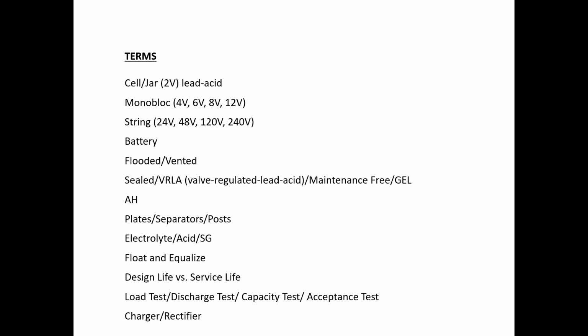Flooded and vented. We're going to talk about the two different technologies. From what I saw of your assets, primarily you are sealed valve regulated lead acid, and sealed is a misnomer. They are not sealed. They do have pressure release valves on them, but again, it was a marketing thing that was done years ago. Same thing with that maintenance-free moniker that was used to push that technology when it was relatively new. And then gel. A lot of people think gel and AGM or valve regulated are necessarily the same thing. Gel actually uses silica to immobilize the electrolyte. So in an AGM, absorbed glass mat, or valve regulated battery, you don't have acid sloshing around.